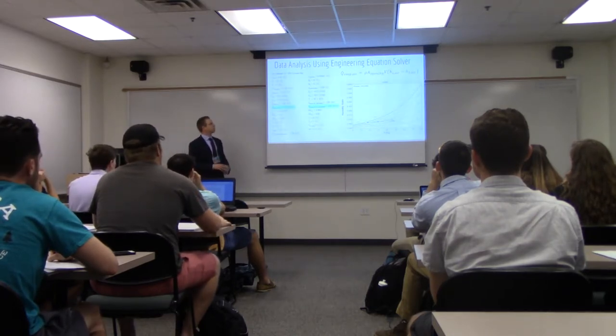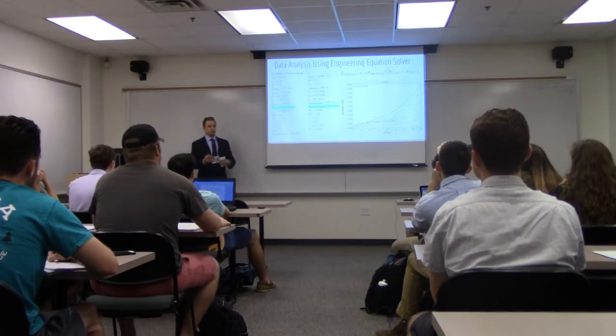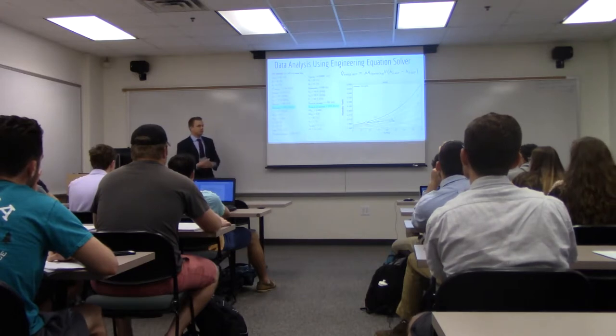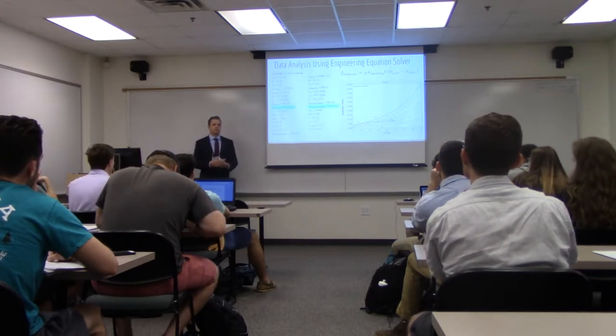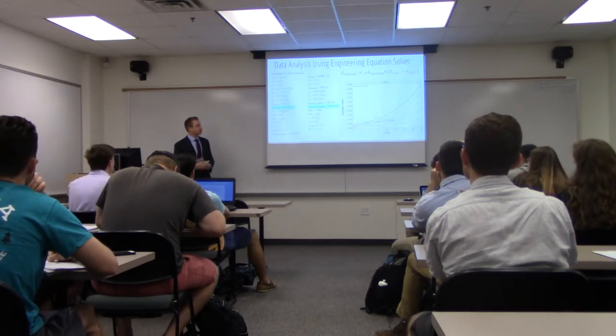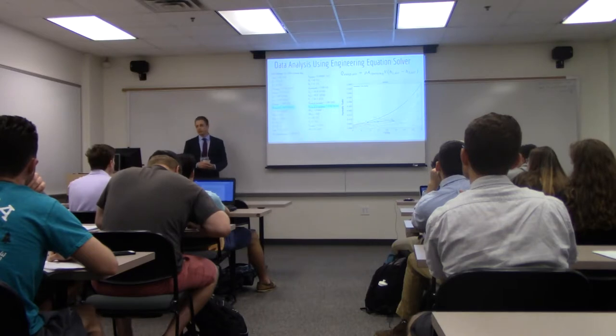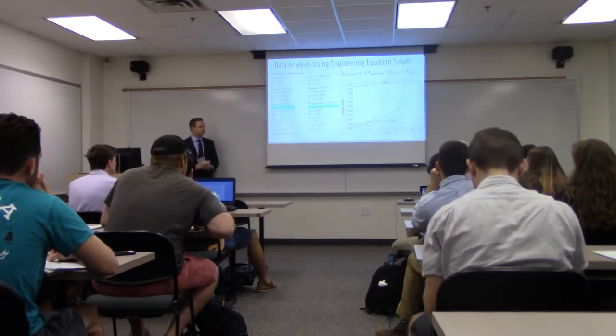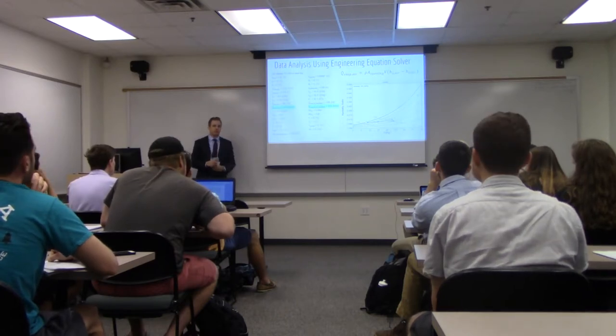After you put all your knowns in and get all the equations right, you click solve and it pops out a screen with all the answers in a matter of a second. The main thing we want to focus on is Q_EVAP_air — this is the amount of energy in the air that can be removed. There are two values: calculated and pressure-calculated. The pressure-based calculated value is higher because it's ideal and ignores heat losses to the surroundings and possible condensation formation. On the right is a psychrometric chart showing changes in relative humidity, humidity ratios, and enthalpy. You can tell it's a cooling process because from points two to three there is a massive temperature drop and enthalpy drop.